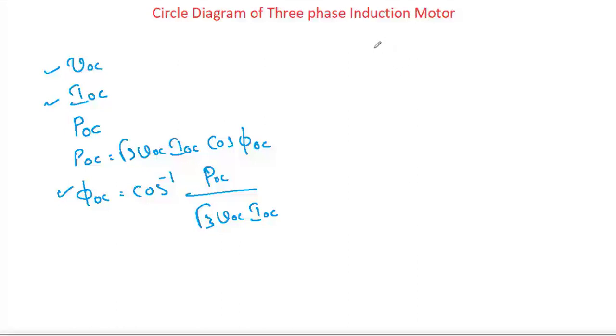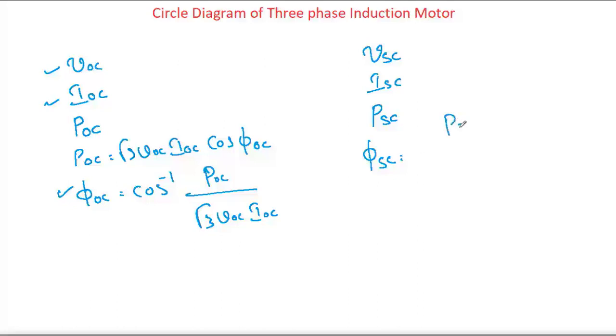Similarly, we should conduct an SC test, that is a block rotor test. From the block rotor test, we need to get the value of V_SC and I_SC. By placing a wattmeter, we can measure the power consumed during the short circuit test. After that, we need to find the power factor during the short circuit test: cos φ_SC = P_SC divided by (√3 × V_SC × I_SC). These values are required to draw the circle diagram of the three-phase induction motor.